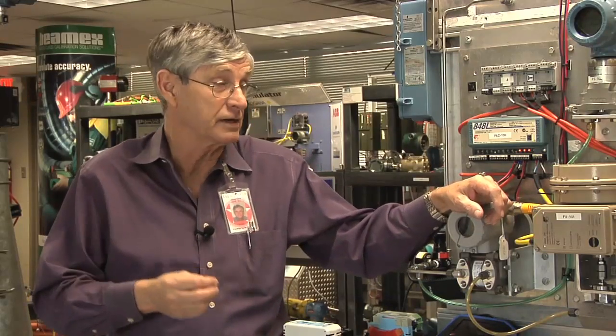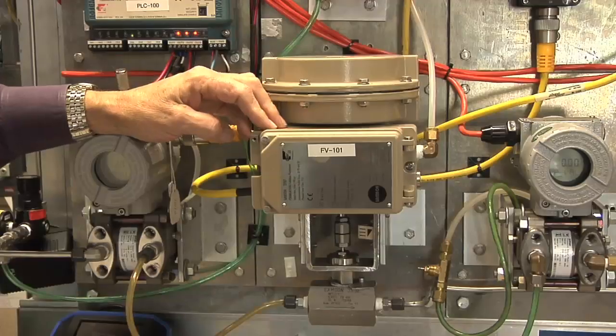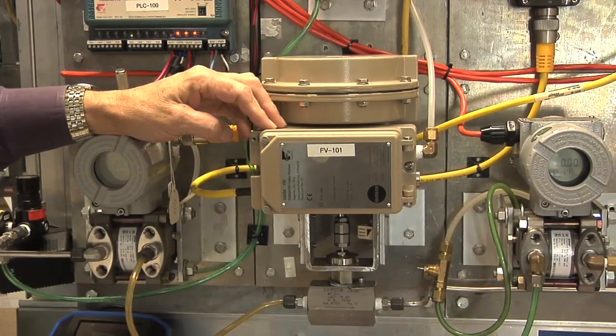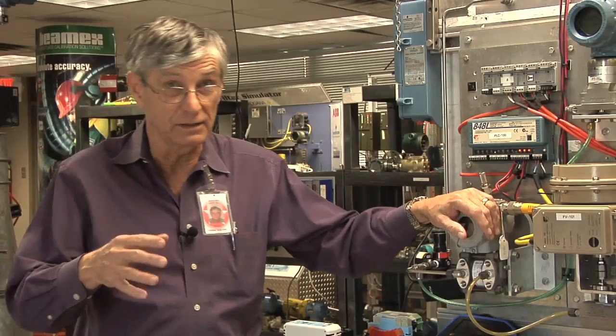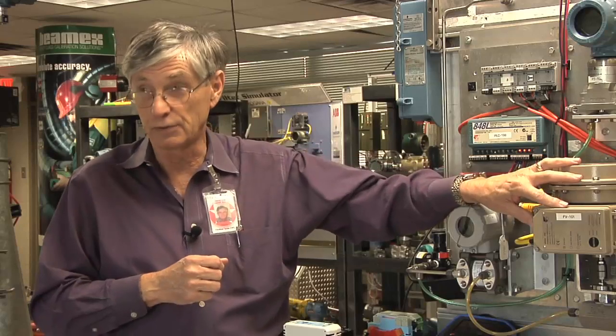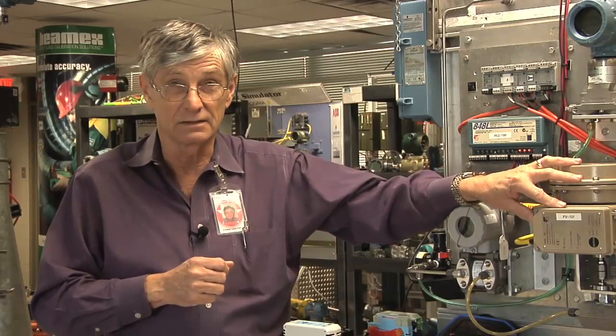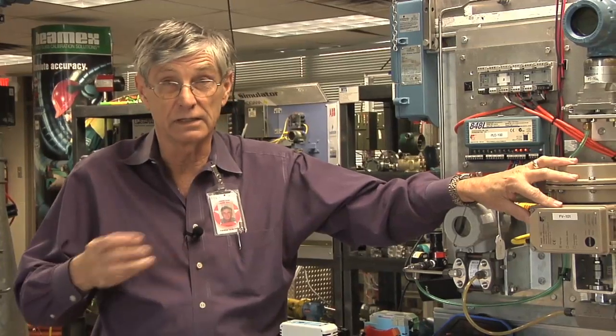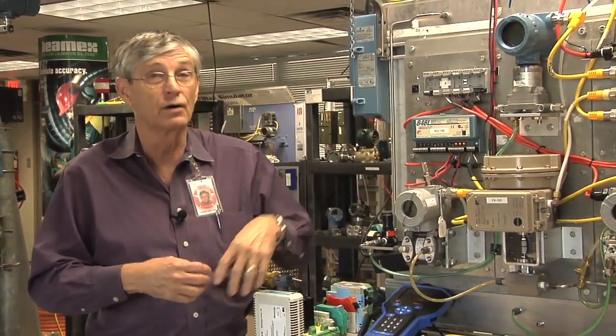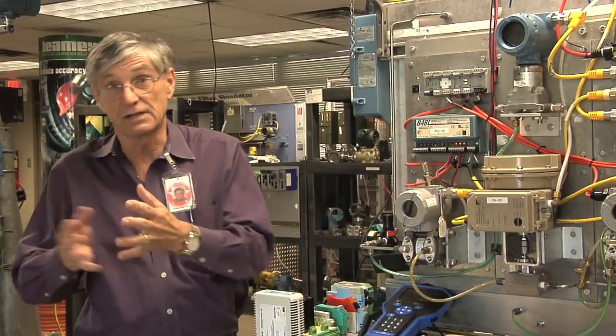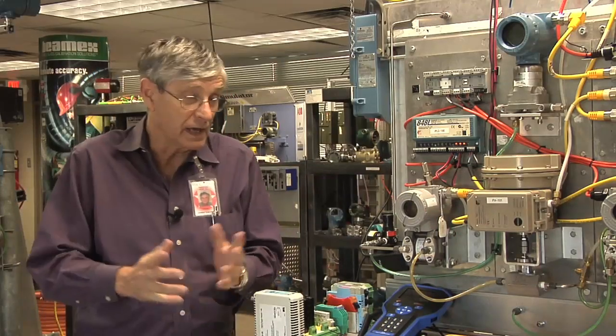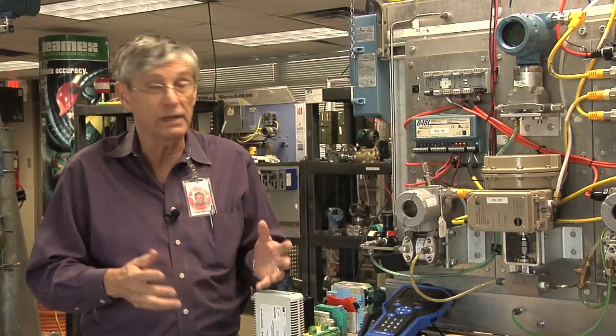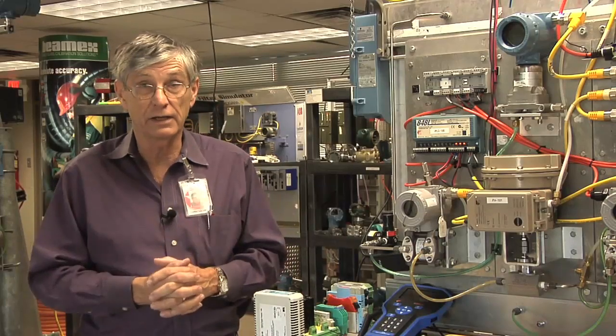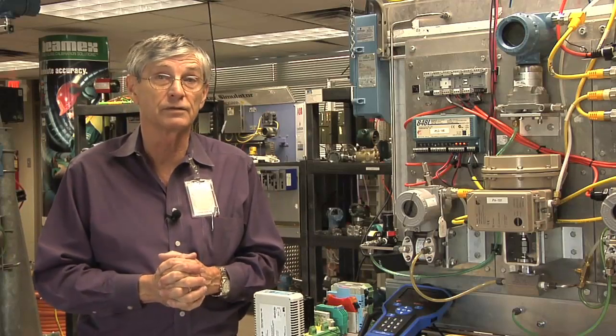The most common, almost accepted practice is we'd like to put the PID in the valve. It does not have to be there. It could be, in this case, in the transmitter, or in reality, even in another device, but that wouldn't normally make a lot of sense. So in this case, we're going to put the PID control in the valve and then load it, build it, configure it, and see what steps are required to get the PID out of the host and placed into the valve, and then of course test the operation to see that it works effectively. Once you've seen the success of doing that, you can make decisions about what other areas of the plant you may want to begin using control in the field with.